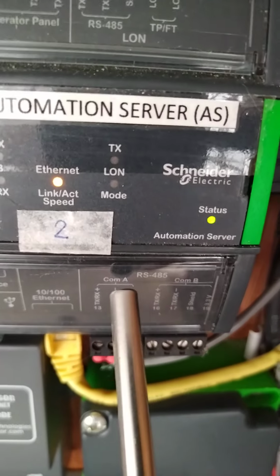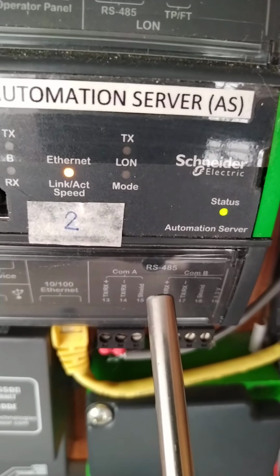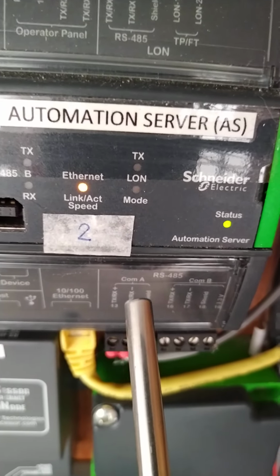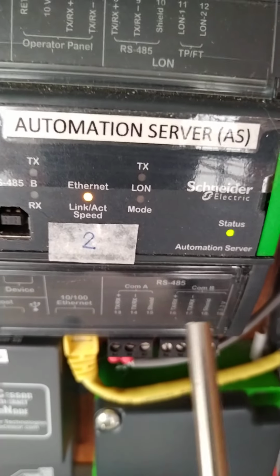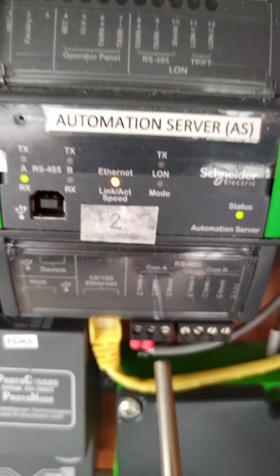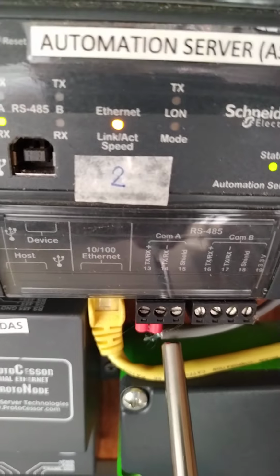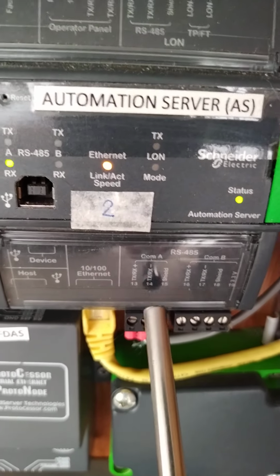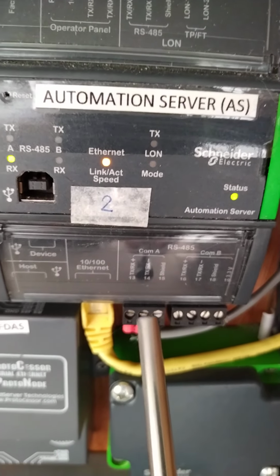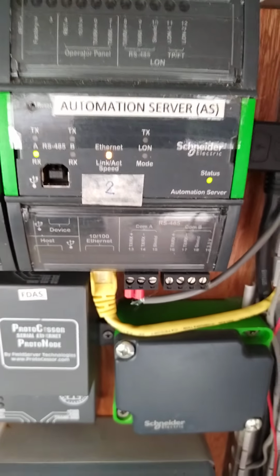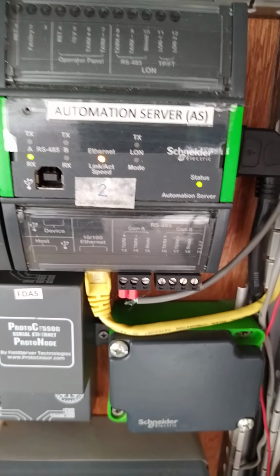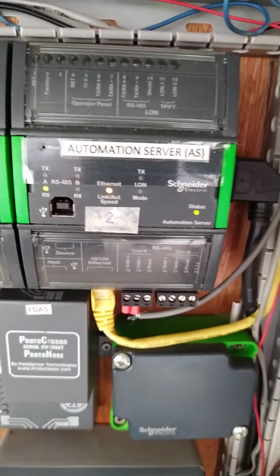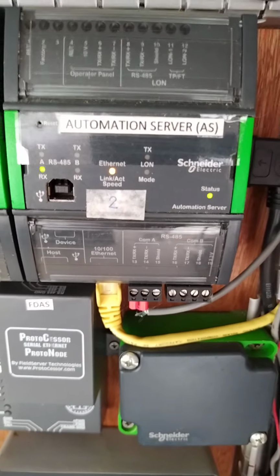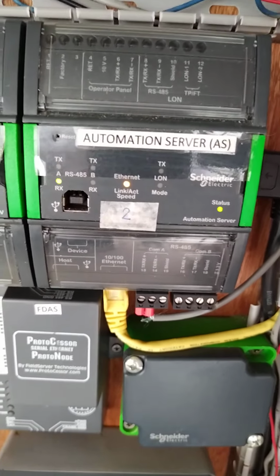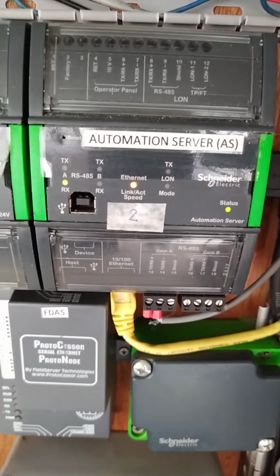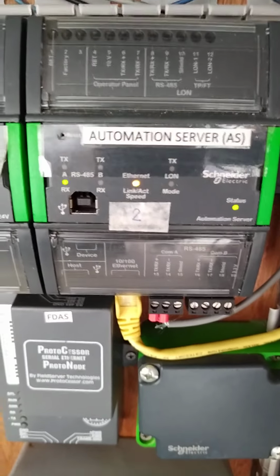I am using an RS485 cable, then my communication port A and port B. So I have connected my three BACnet controllers here. You just need to follow the correct polarity. My three BACnet controllers are connected in a bus topology or daisy chain connection, using BACnet MSTP network for the three BACnet controllers.